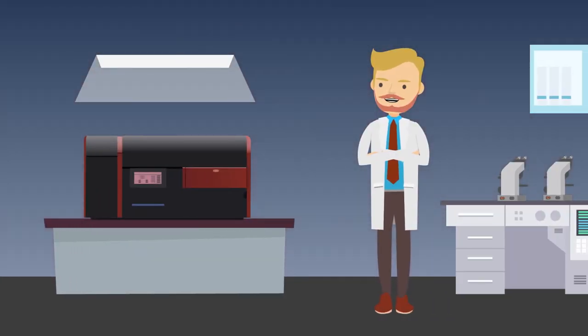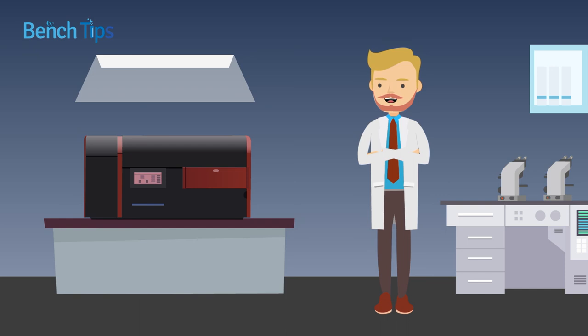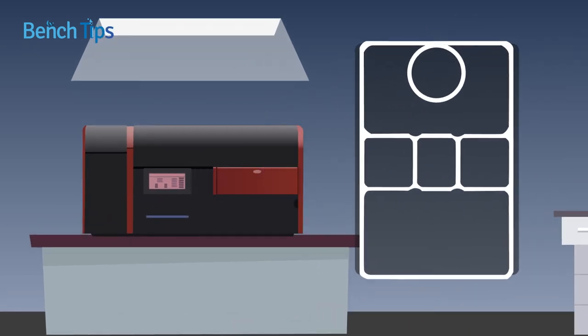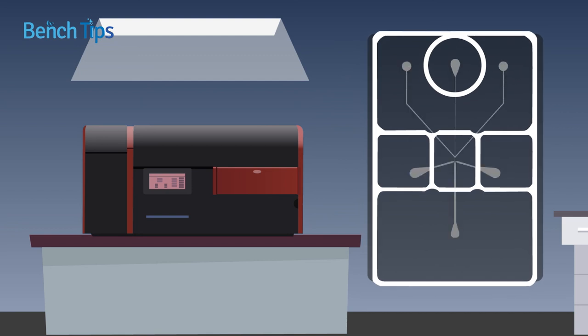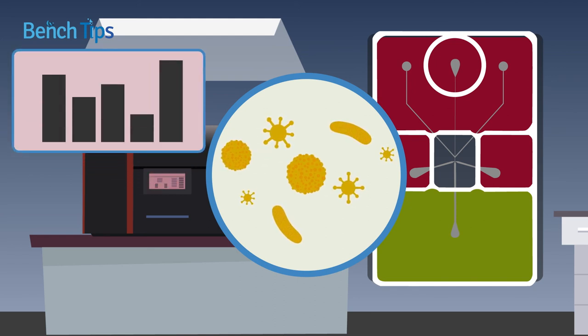As well as providing better quality cells, flow shift cell sorting offers several other advantages over conventional techniques. First, because the technology is based around a small, disposable microfluidic chip, the sample, sheath fluid, and waste are contained throughout analysis and sorting. This removes the risk of sample-to-sample contamination or contamination to the instrument itself, enhancing data quality.